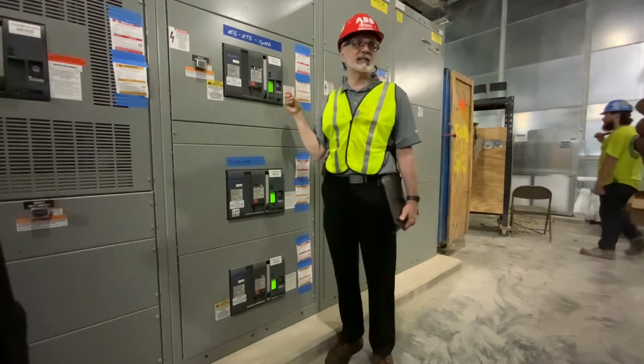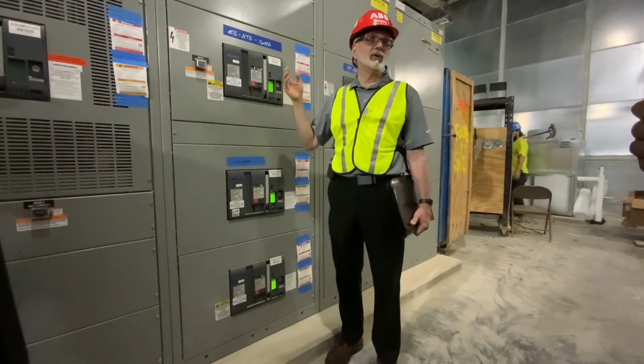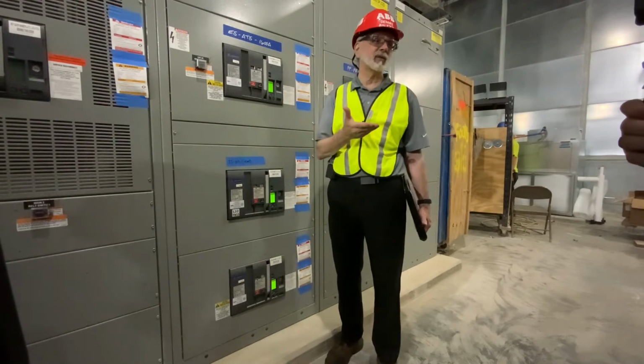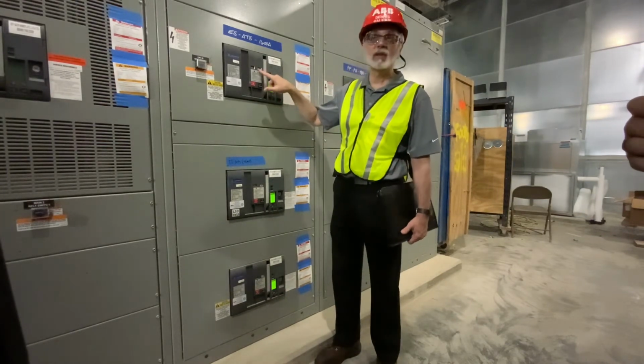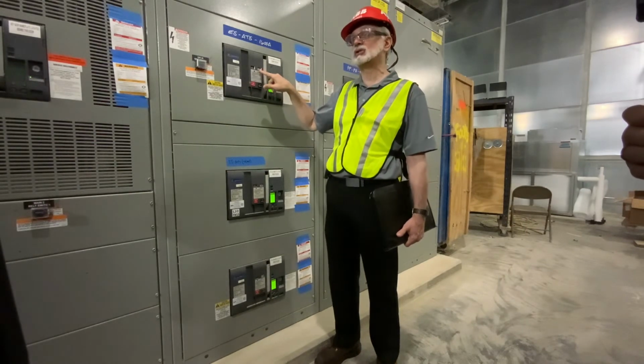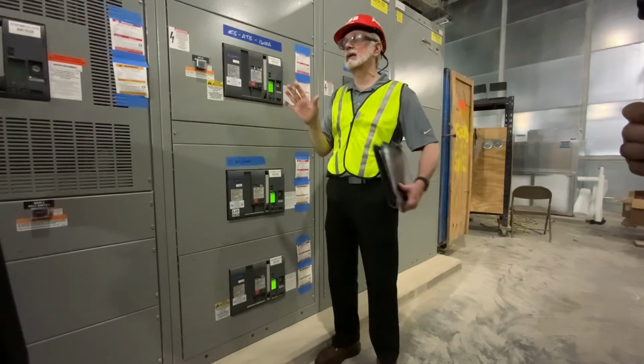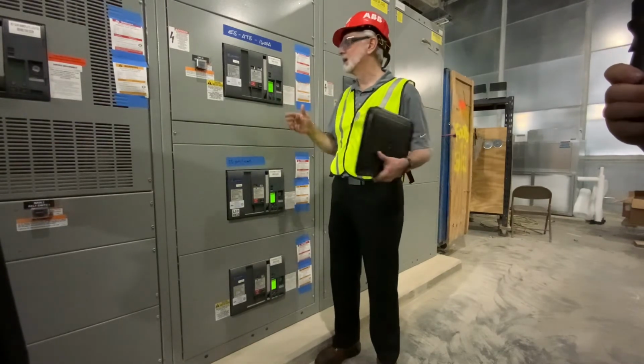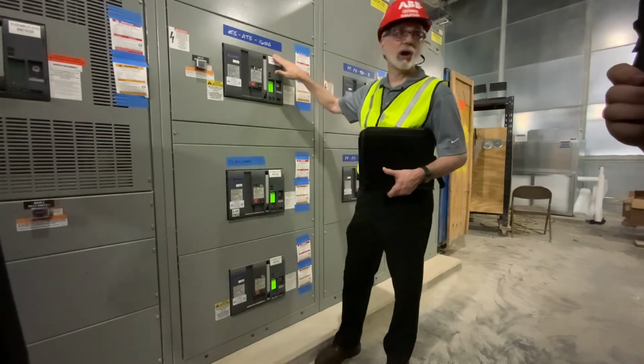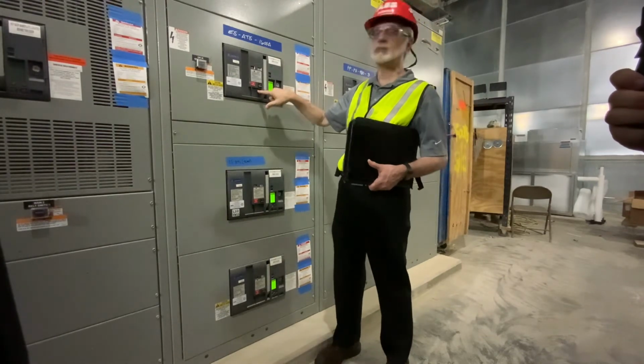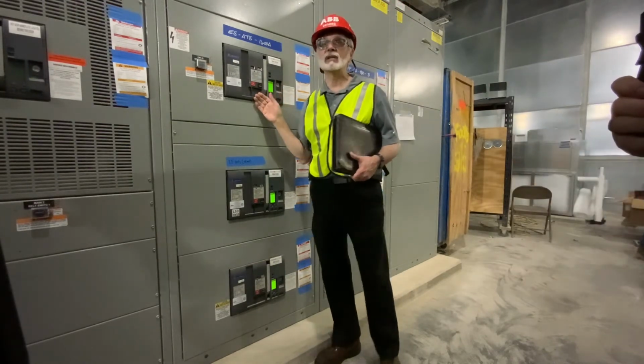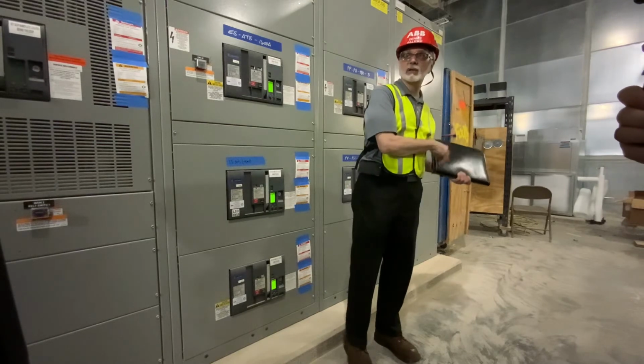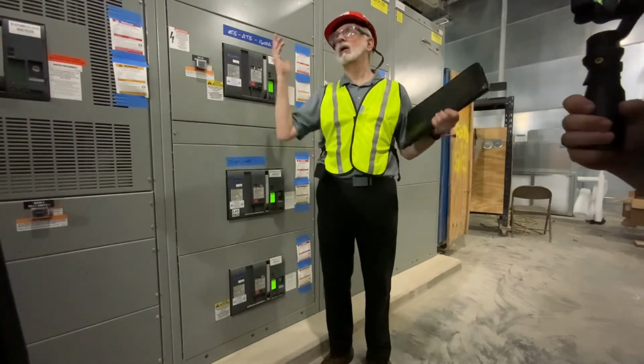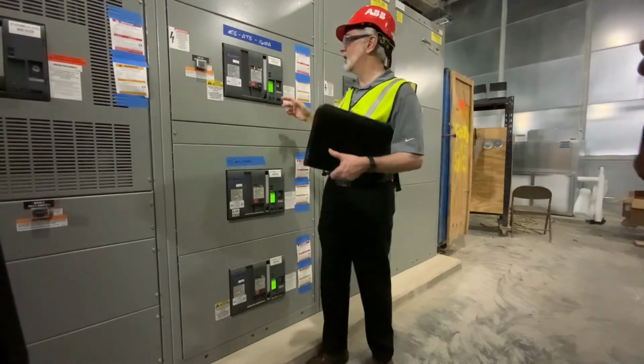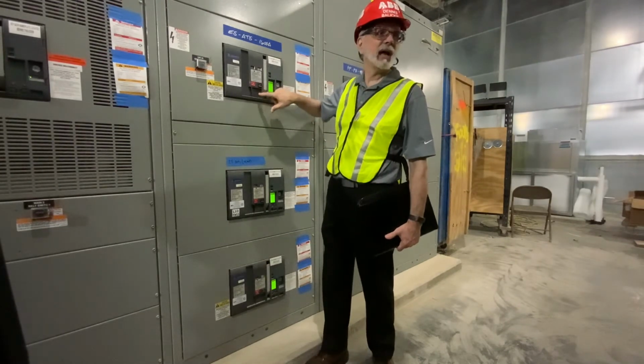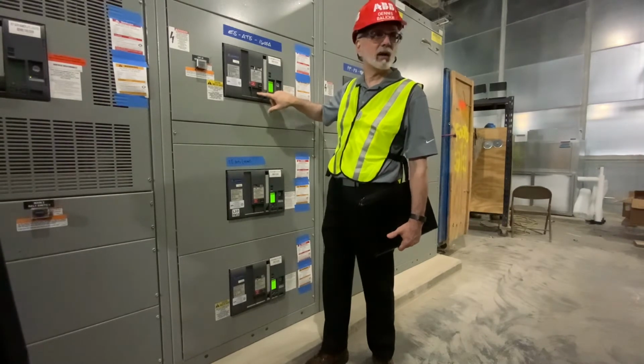So the nice thing about this is you do get a free reclose. So you can open, close, open, because we do that a lot of times for automatic throw over. But again, the important thing is are these springs charged or discharged? And the only reason I bring that up is you may have a situation at 2 in the morning where somebody is doing work on this automatic transfer switch, let's say. So they're going to push this breaker open, they're going to do their lockout tagout procedures, they're going to do their work on their automatic transfer switch, then they go away, and then, let's say, oh yeah, I forgot, you got to do that. So then you come back here, and now you're trying to hit the close, and you're like, I don't understand. I'm pushing the button, why isn't this breaker closing?